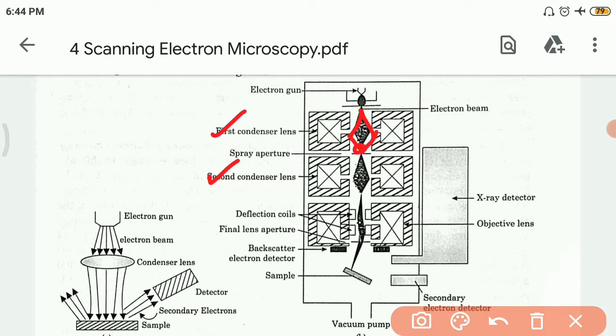Thereafter we have pairs of scanning coils or deflector plates. These deflection coils will deflect the electrons in the X or Y direction, so that the electron beam will scan the sample which is placed at the bottom.